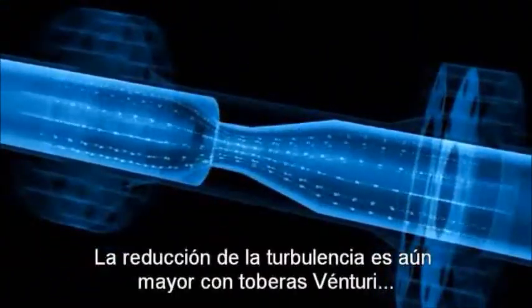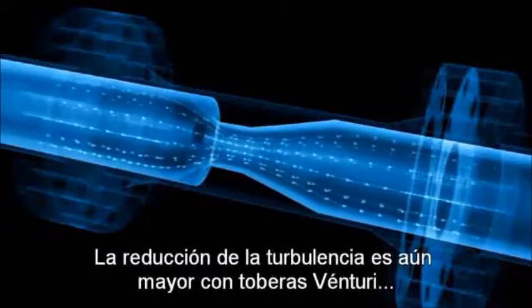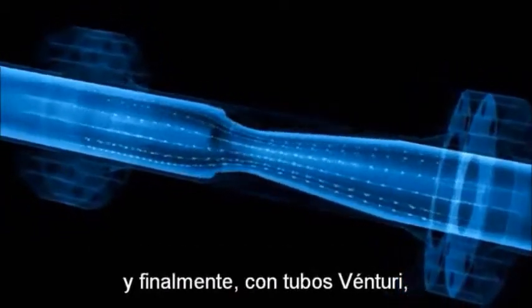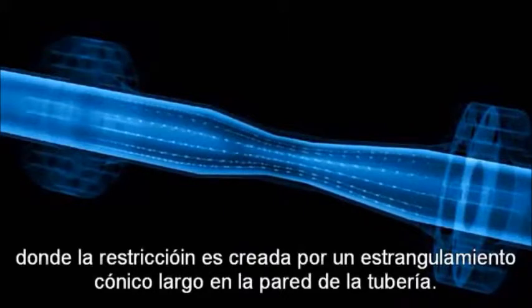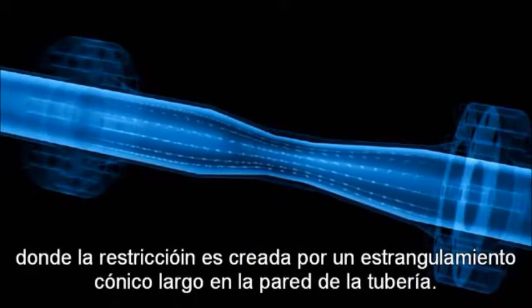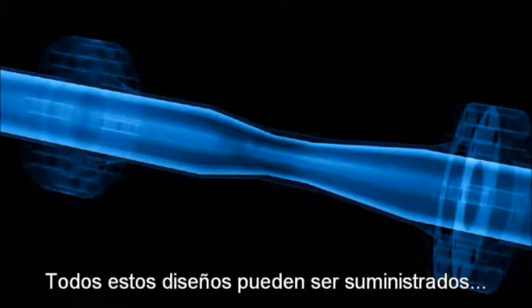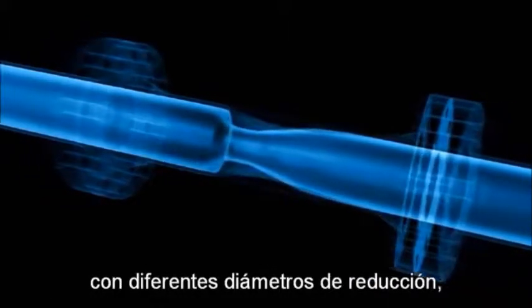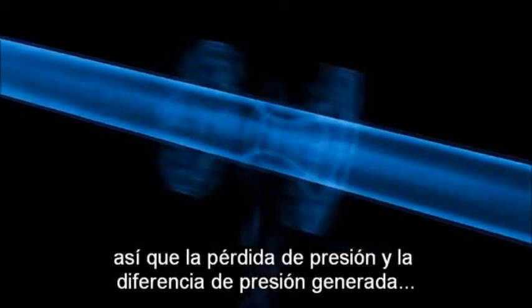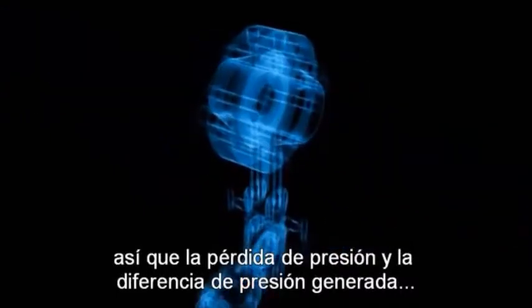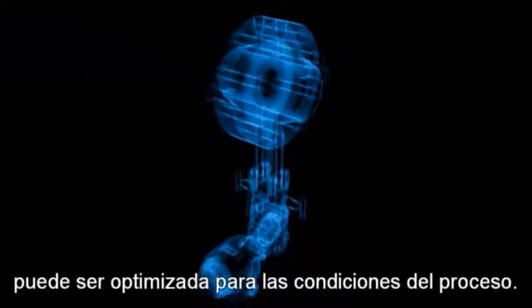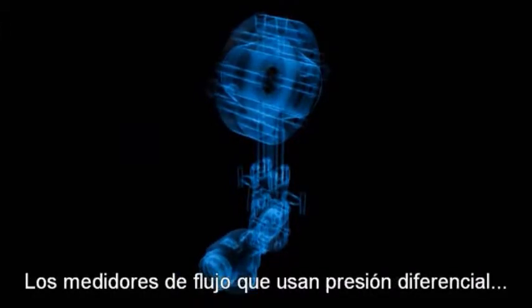Turbulence reduction is even greater with Venturi nozzles, and finally with Venturi tubes, where the restriction is created by longer conical constrictions in the pipe wall. All these designs can be supplied with different restriction diameter sizes, so that the pressure loss and the differential pressure generated can be optimized for the process conditions.